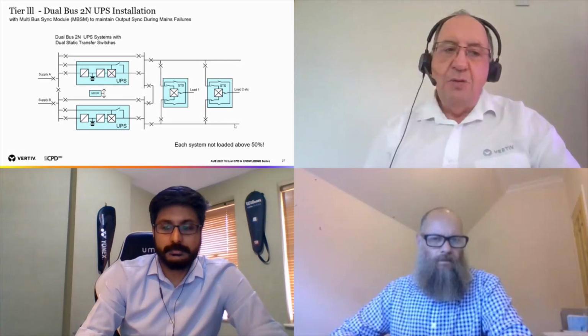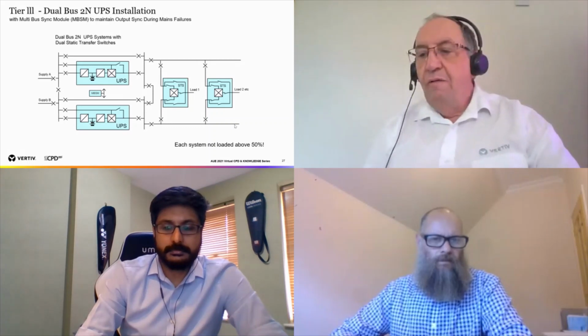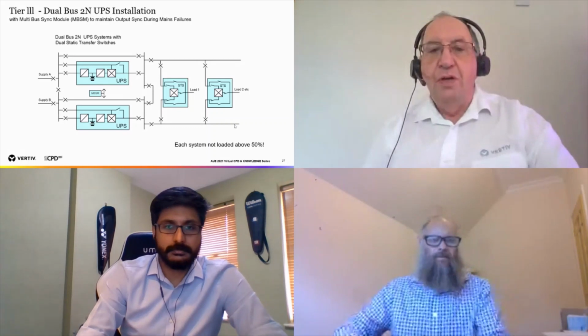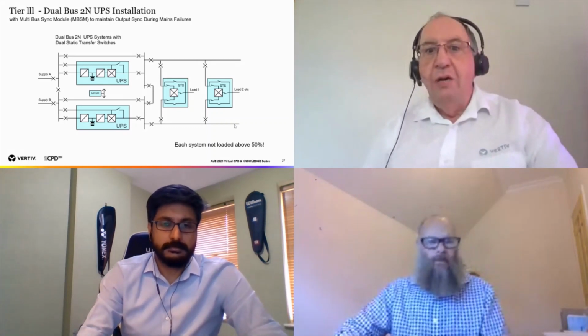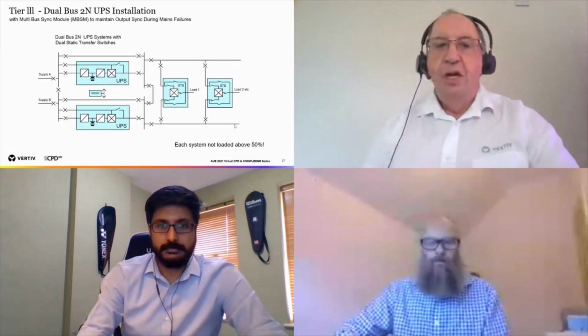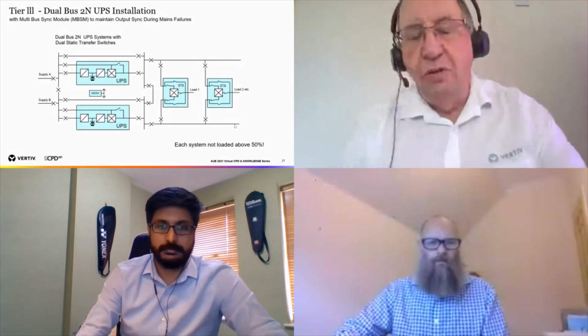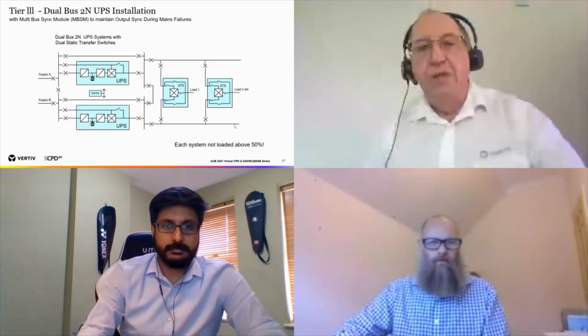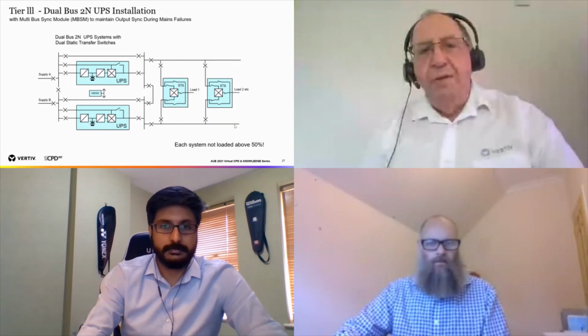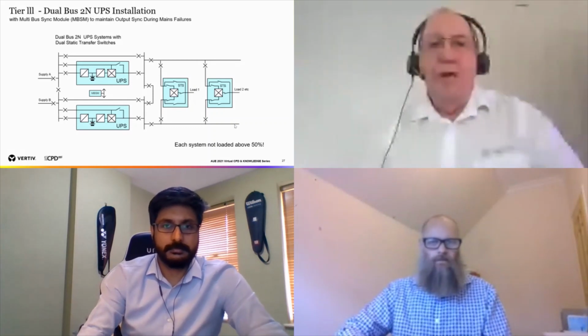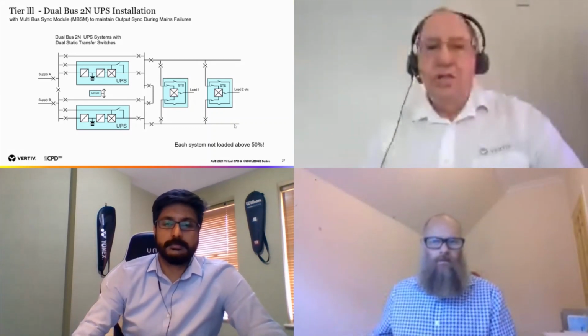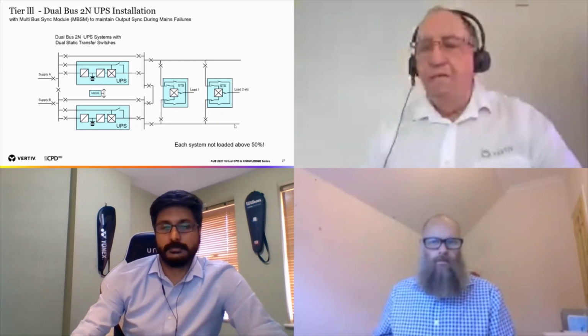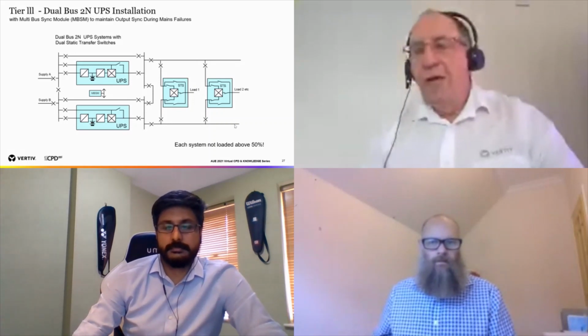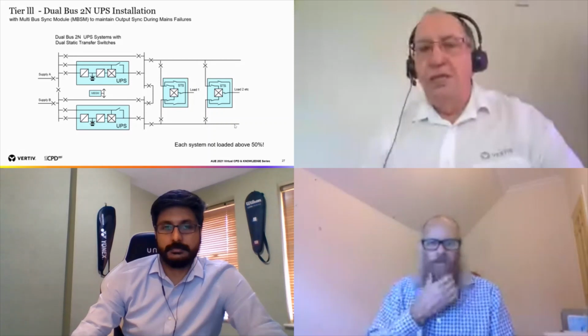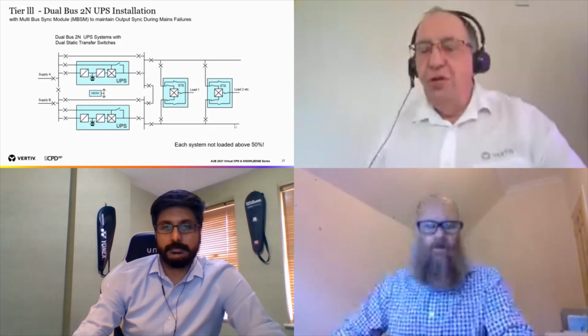So a static switch is a system for doing very fast transfers between 2 incoming power supplies, and they range in all sorts of sizes, right up to 5,000 amps. So that is a way of generating quite a good system, but this is not fault tolerant. So if we had a major fault on this system, we might still lose the load.